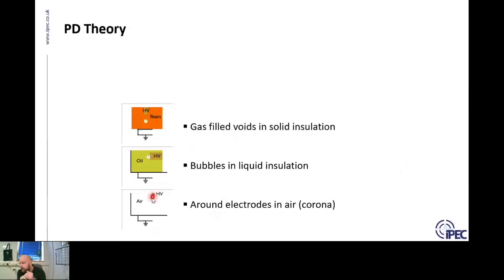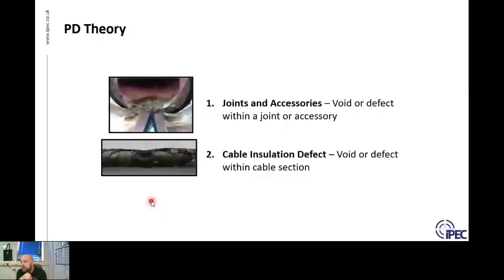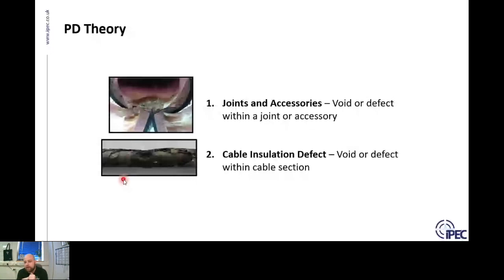In cables, the main places you'll find a defect are on the joints and accessories. You can get PD occurring in the pure cable insulation — it's much more common in older network types like oil and paper cables. In modern networks using XLPE or polymer-based cables, the joints and accessories — the man-made bits that an engineer terminates on site — are where defects are found, because modern manufacturing techniques mean pure cable quality is very high and cables go through stringent tests on production and commissioning.